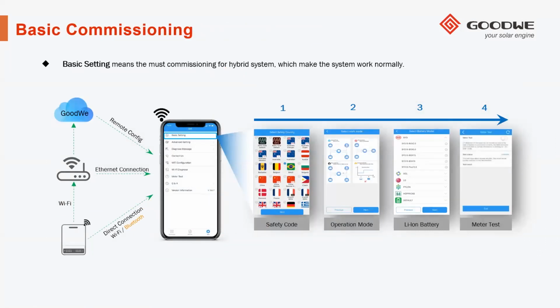So the basic commissioning is done with the PV Master application on your phone, which is available on Android and iOS. In basic settings, there is a password. That password is Goodwe 2010. When you connect your phone to solar Wi-Fi, the inverter's Wi-Fi, it has a password, which is 12345678. And then we go into basic commissioning. You'll select your country code, your operation mode and your lithium-ion batteries. And once that's all done, you have your meter test.